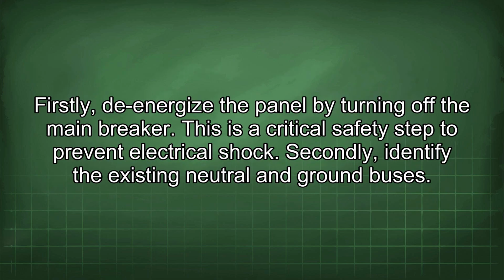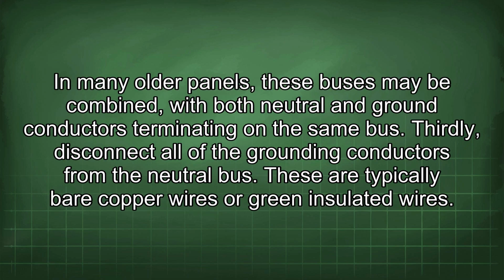Firstly, de-energize the panel by turning off the main breaker. This is a critical safety step to prevent electrical shock. Secondly, identify the existing neutral and ground buses. In many older panels, these buses may be combined, with both neutral and ground conductors terminating on the same bus.